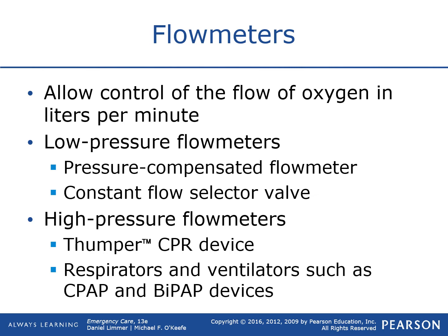You have high pressure flow meters. Those are ones that you usually use for ventilators and CPAPs. Those can go up to 25 liters per minute. So most of the time we're going to be seeing the low pressure flow meters, but we do have certain circumstances if you're using BiPAP or a ventilator that we will have a high flow meter. That just means that we can deliver more oxygen.